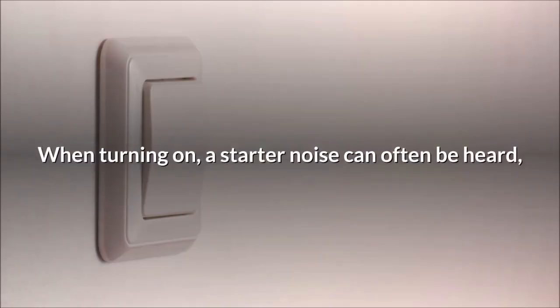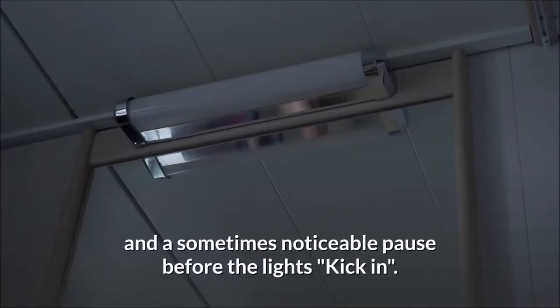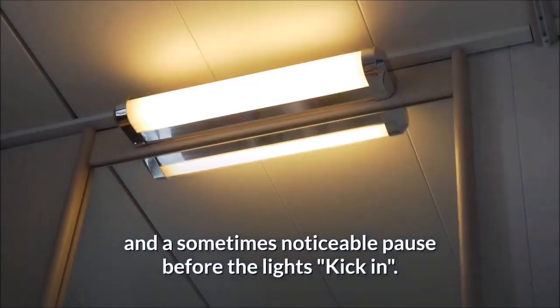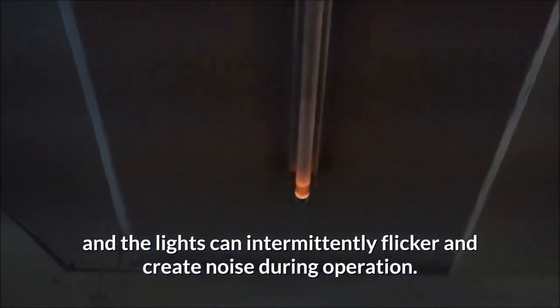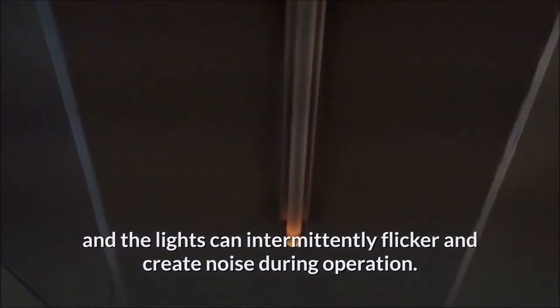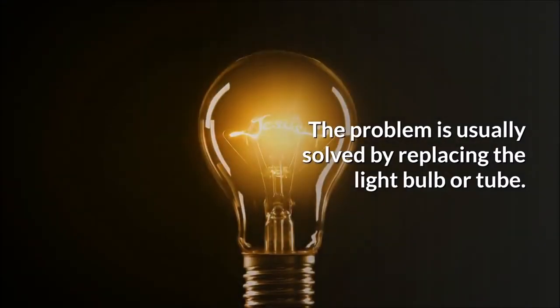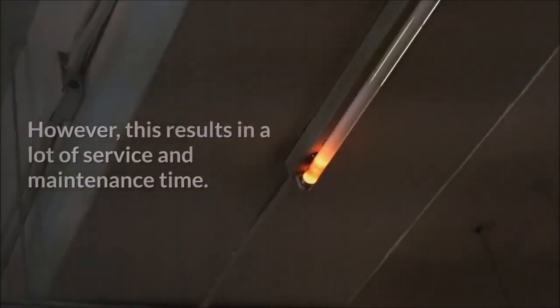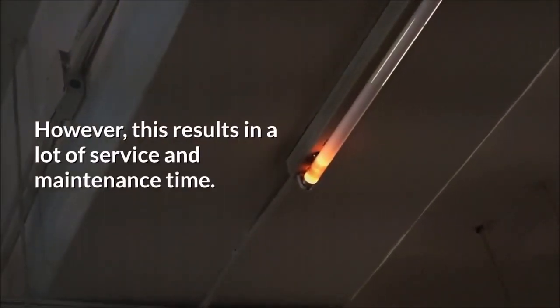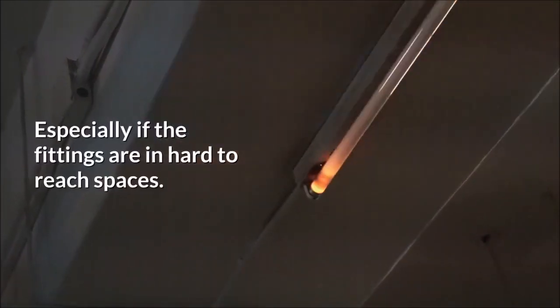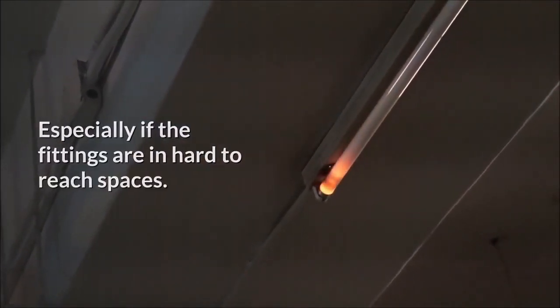When turning on, a starter noise can often be heard, and a sometimes noticeable pause before the lights kick in. When they age, this delay prolongs, and the lights can intermittently flicker and create noise during operation. The problem is usually solved by replacing the light bulb or tube. However, this results in a lot of service and maintenance time, especially if the fittings are in hard-to-reach spaces.